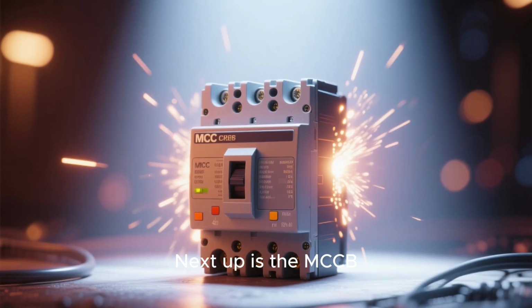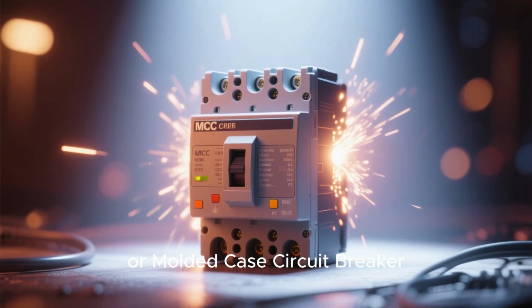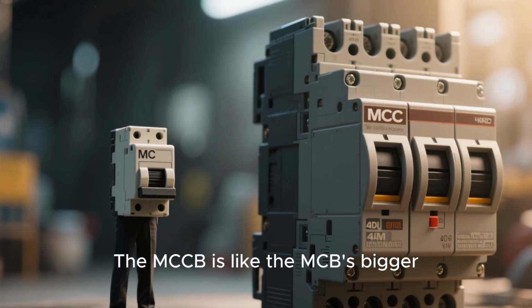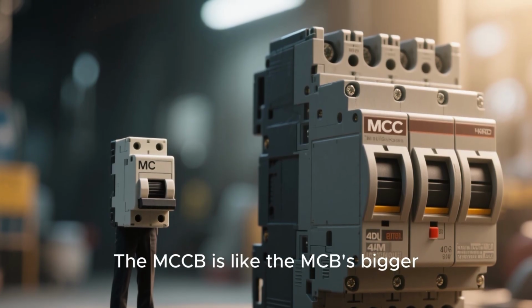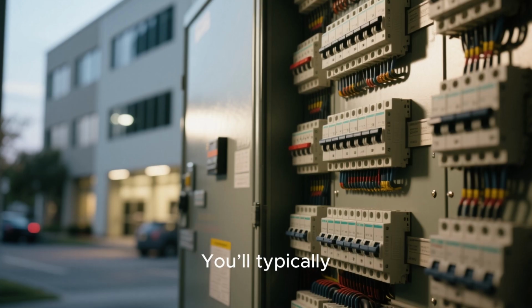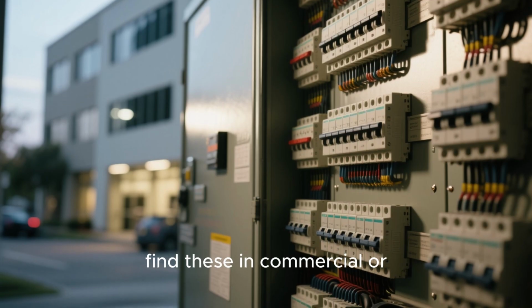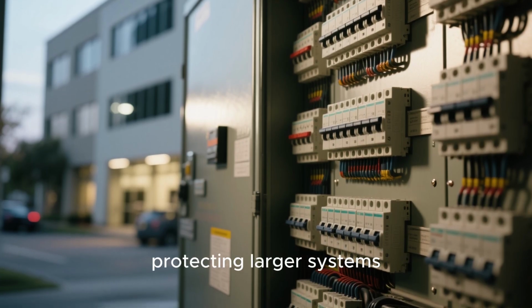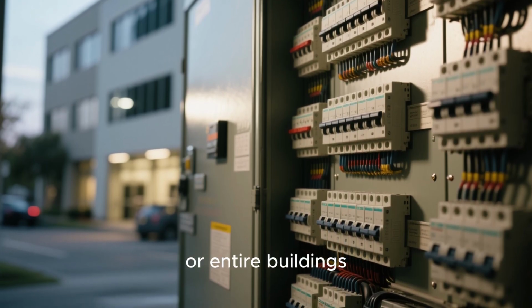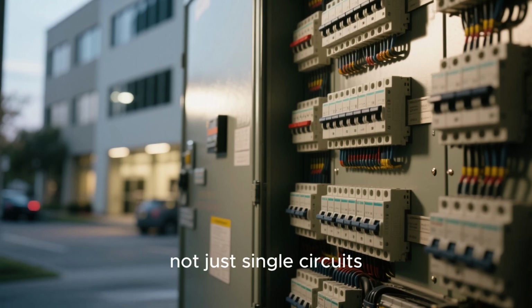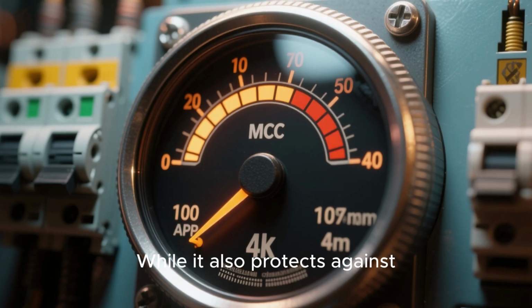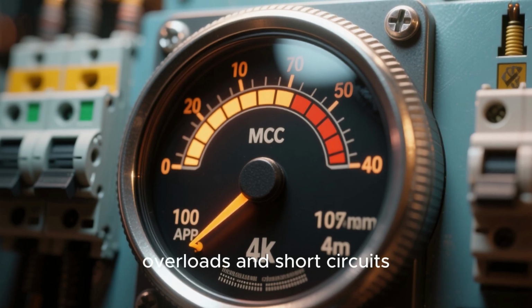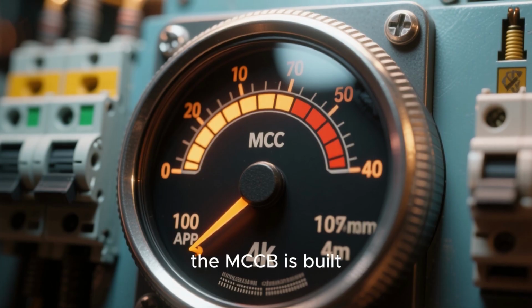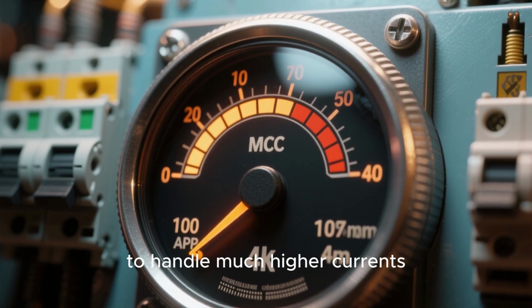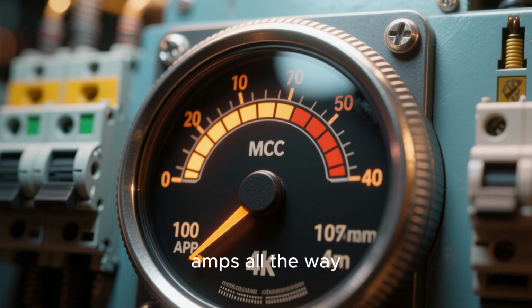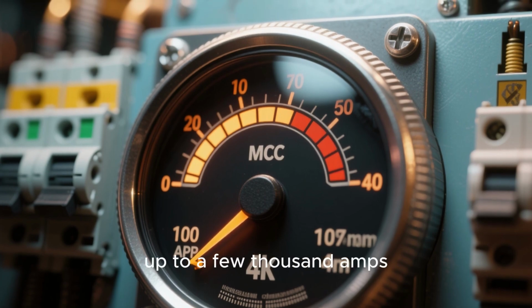Next up is the MCCB, or Molded Case Circuit Breaker. The MCCB is like the MCB's bigger, tougher sibling. You'll typically find these in commercial or industrial settings, protecting larger systems or entire buildings, not just single circuits. While it also protects against overloads and short circuits, the MCCB is built to handle much higher currents, from around 100 amps all the way up to a few thousand amps.